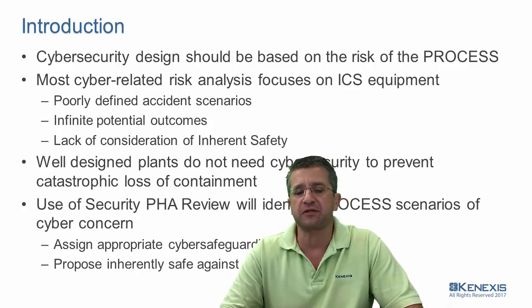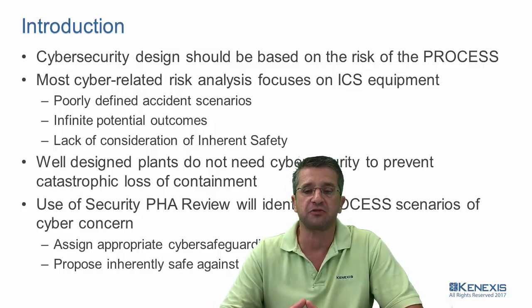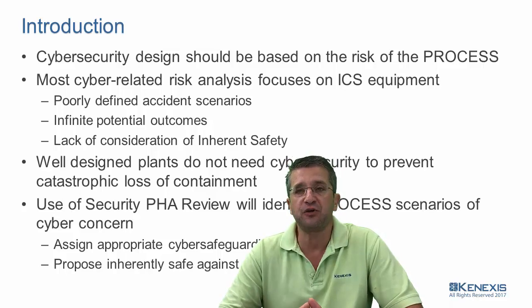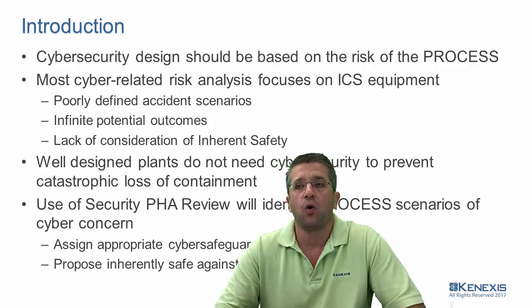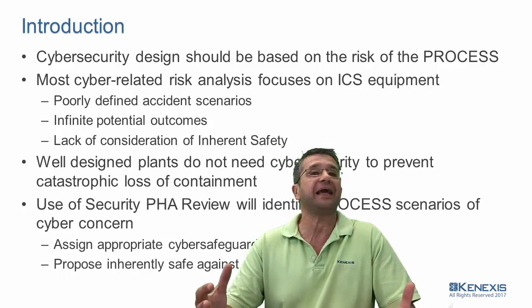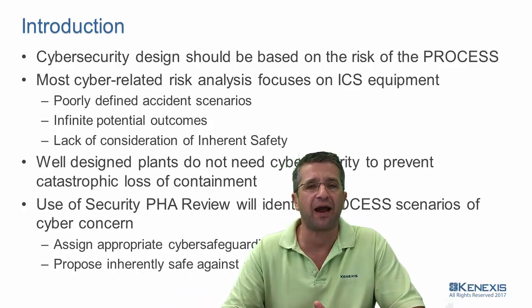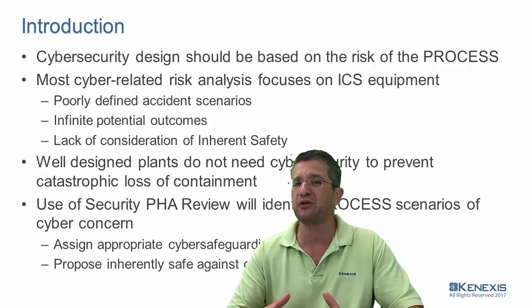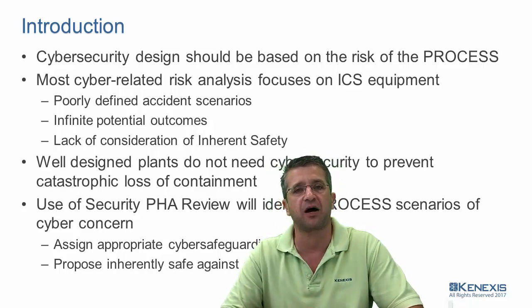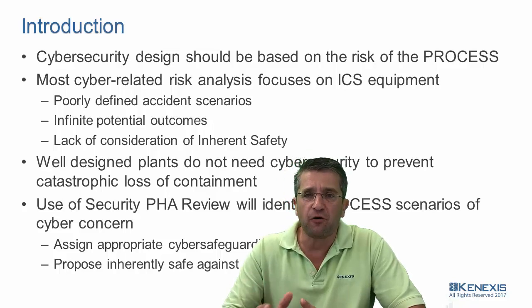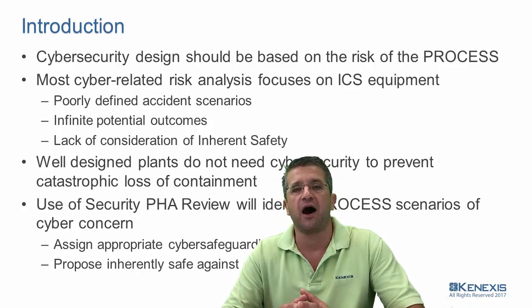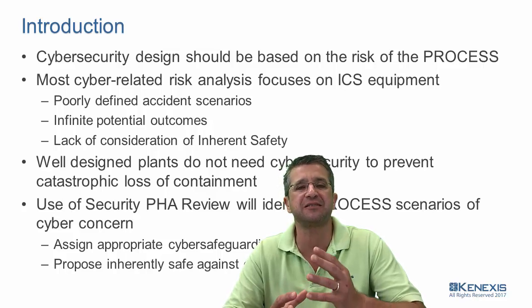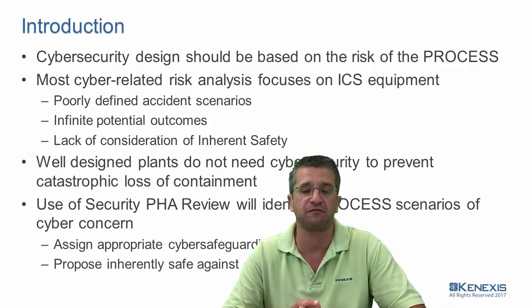When you only focus on the ICS equipment, there are a lot of problems that result, like a poor definition of what accident scenarios are possible and infinite potential outcomes. If you have the possibility of a man-in-the-middle attack on your historian machine, literally anything can happen. Your cyber HAZOP, your CHAZOP, your cyber PHAs really don't get into that, where your existing HAZOP documentation can do a very good job of it. Also, focusing on the ICS equipment prevents you from considering inherent safety, which is the best way to make your plant safe.